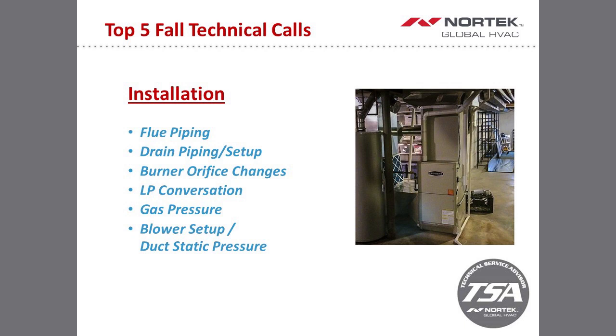So on the blower setup, what I'll say is that we don't preset anything from the factory on the furnace side. So especially on the 2-stage equipment regarding dip switches, all the dip switches are going to be in the off position. So if you were to actually look at the blower chart, you're only going to be pushing about 400, maybe 500 CFM, depending on your duct static pressure. This is a very common call that we get into tech: techs will start up a new furnace and they'll call us and say the blower's hardly pushing any air.